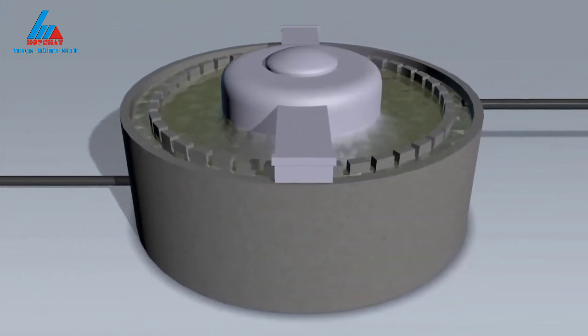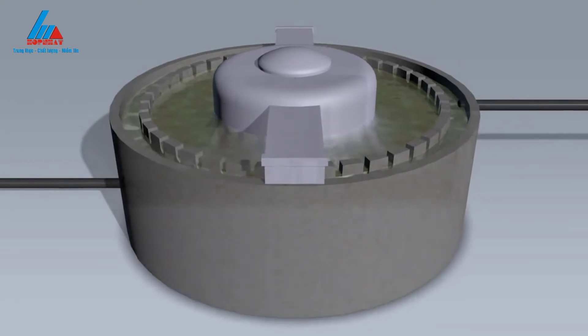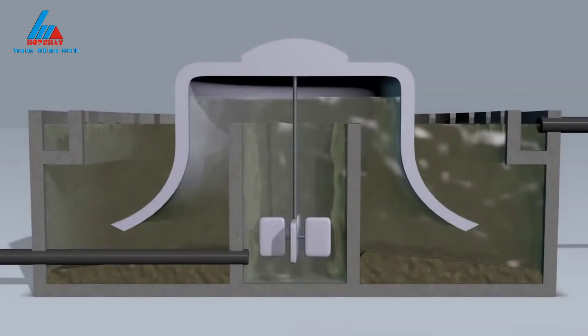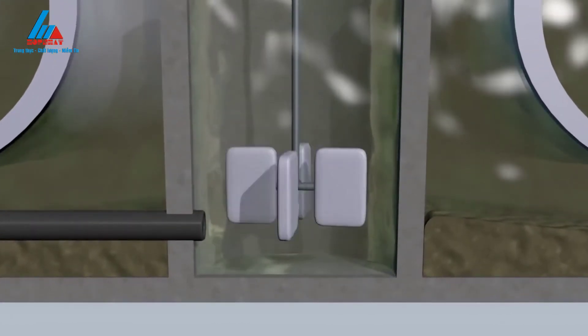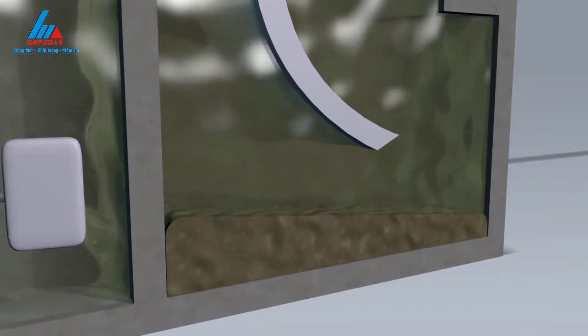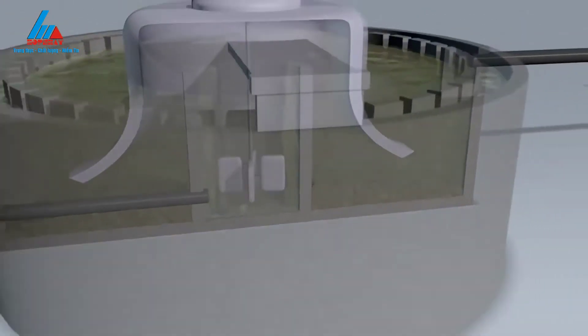After that, the water goes through a softening process. While not a health risk, hard water can cause undesirable mineral buildup in pipes. A mixture of slaked lime and soda ash is added to the water to precipitate calcium and magnesium, two hard water-causing minerals.